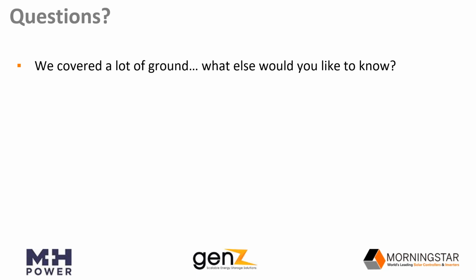Look, I'll provide some answers from genZ. So with our rack-mount module, say you've got 10 on your server rack, and say one of them has failed. The circuit breaker would actually trip, and you would see it, and you'd probably notice that you have less capacity drawing from the battery bank. So that's how you could identify there's a fault in the battery: the circuit breaker trips.